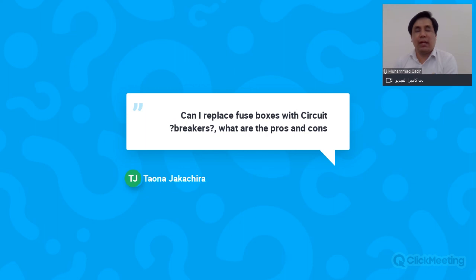In case you need a breaker for switching, yes, you can use one, but fuses are not required, and it is not recommended to use fuses when you are using a Huawei solar inverter.